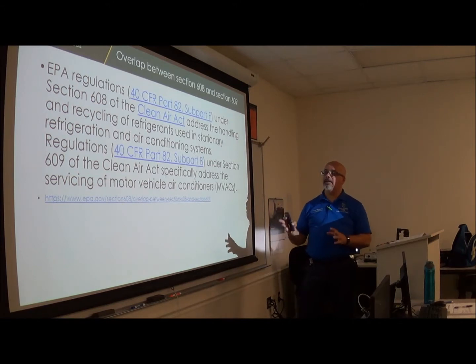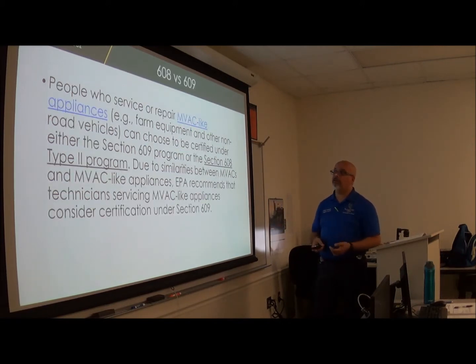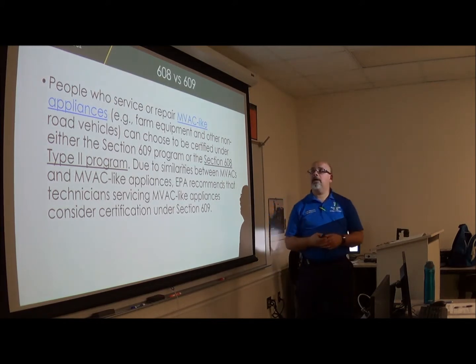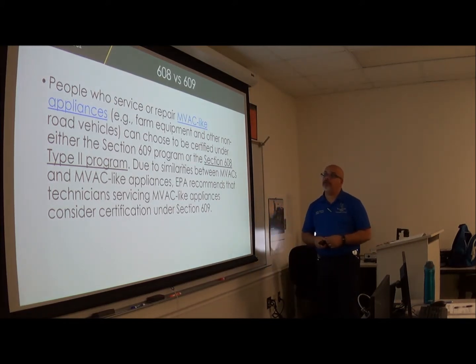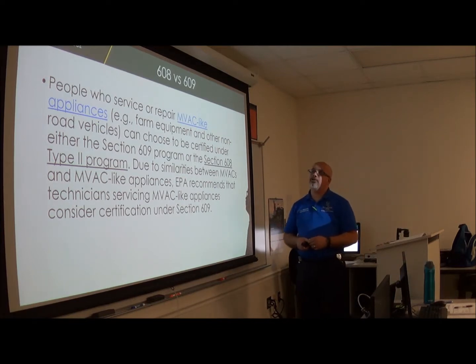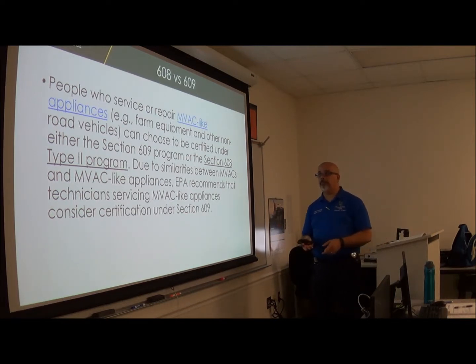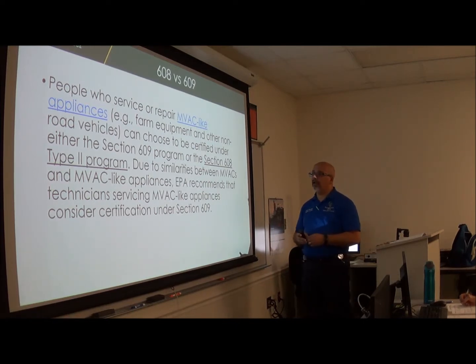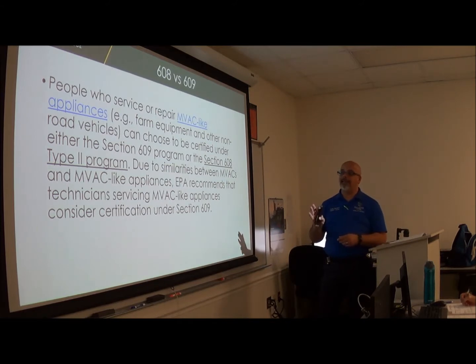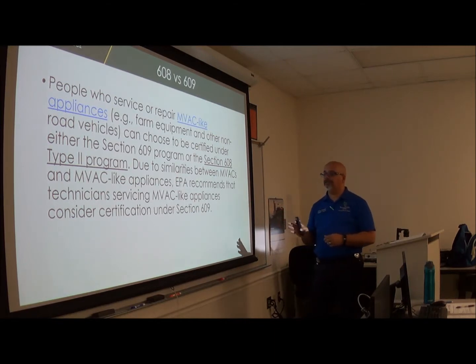And this link, I sent that page to all of you in the email that I sent when you registered for the class. So, 608 versus 609. People who service or repair MVAC-like appliances, for example farm equipment and other non-road vehicles, can choose to be certified under either the Section 609 program or the Section 608 Type 2 program. Due to similarities between MVACs and MVAC-like appliances, EPA recommends that technicians servicing MVAC-like appliances consider certification under Section 609.